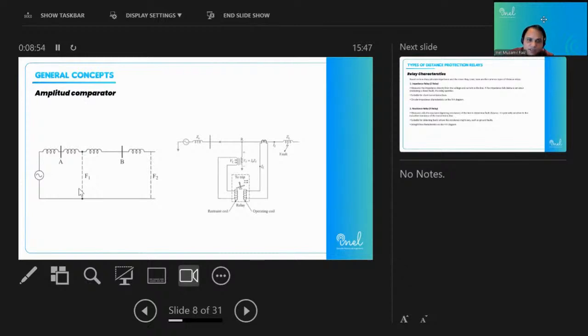So when the transmission line is fixed, like it is 100 kilometers, then its impedance is fixed at the moment when we decide what its length would be. So now we have one quantity which is the impedance of the line, and another quantity which is the impedance measured during the operation. One is a fixed quantity. It depends upon the construction of the conductor. When we have decided the conductor type and that the length will be 100 kilometers, then by these two quantities we will have the impedance of that transmission line.